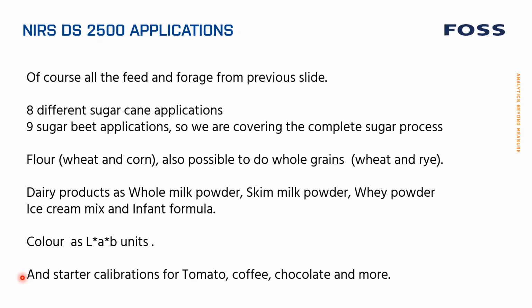Then we can also do color with the DS2500. That is a calibration that's coming out now, any day now. And that will do color with real color units as LAB units. It's not only that we can actually measure in the visible range. Color is different. It's a different calculation than we normally do. So it's not just a calibration, it's a calculation based on the mathematics used for these LAB units. And then we have a number of starter calibrations for different things: tomato, coffee, chocolate, tea, more.